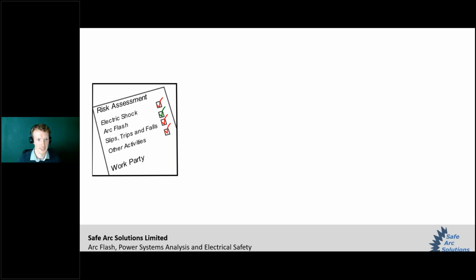So you risk assess this, and the site electrical safety procedures are consulted, and it's determined that you've got the maintenance mode available on this particular switchboard. So you should activate that before any intrusive works commence. If you've got that active, then the site standard Arc Flash PPE, which is rated for 12 calories per centimeter squared, is fine for this task. The Arc Flash boundary for this particular switchboard has been set at 5 meters, so that should be marked or barriered off in some way. And any person not involved in the task should remain well beyond the Arc Flash boundary.